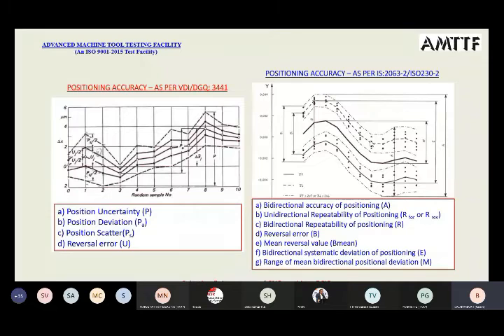That's why you must mention the standard and value you want. VDI/DGQ 3441 uses only the procedure and evaluation, not allowable values, whereas the ISO standard uses both the procedure and the allowed values, as shown in the last slide. So we should be very clear in our mind when selecting a machine what exactly to specify.